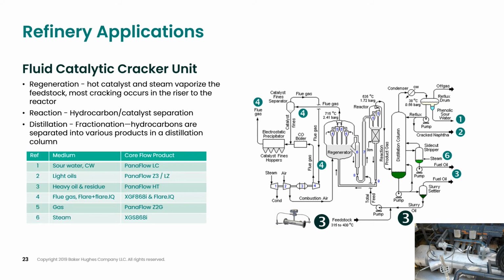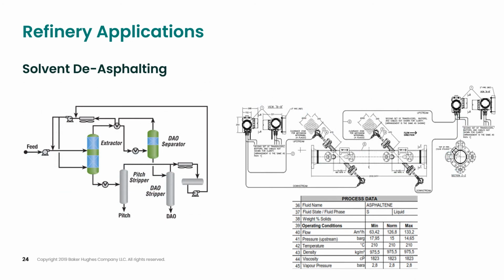For solvent de-asphalting, we have used this specific flow meter design at the feed of the extractor. With this measurement, you can see the high viscosity of 1800 centipoise. Due to the critical nature of the measurement, it was two-path with two separate electronic measurements for this difficult asphaltene line. Employing our BWT technology here, the flow measurement successfully replaced another flow meter measurement technology, which continued to have inconsistencies.